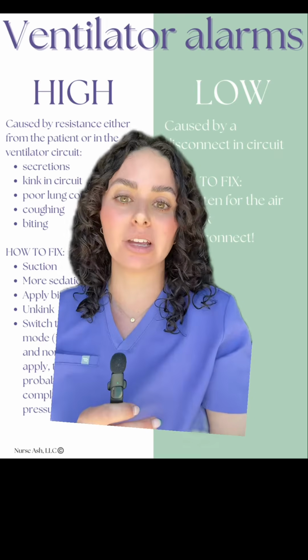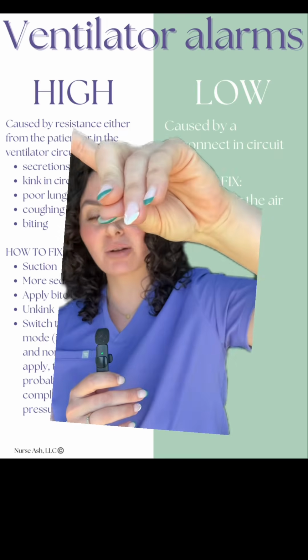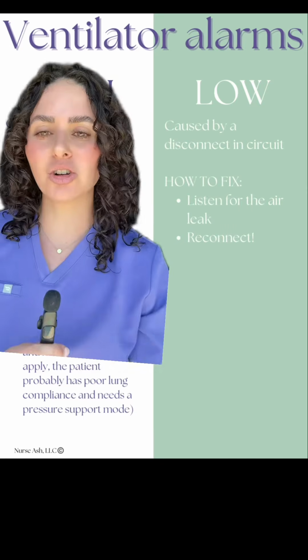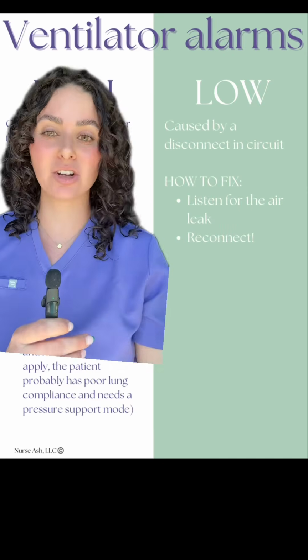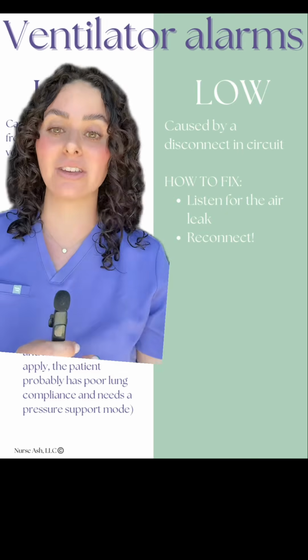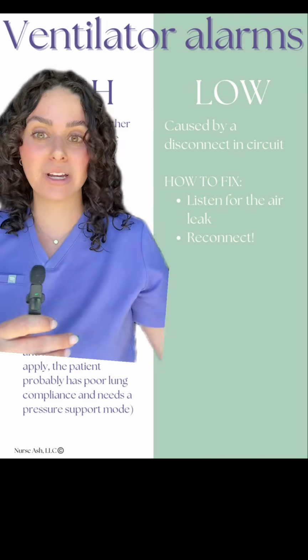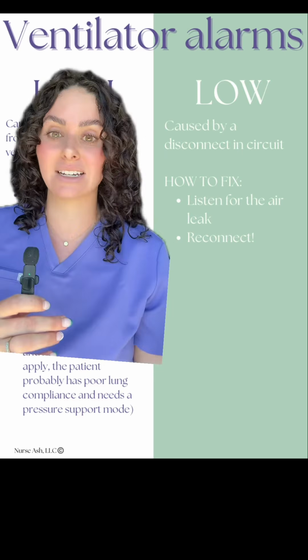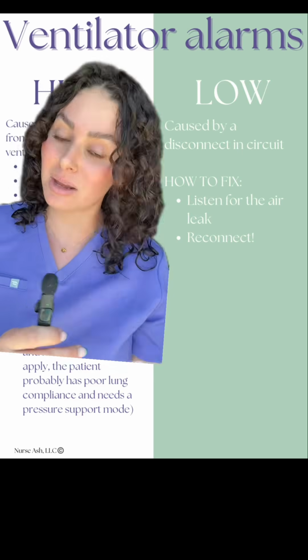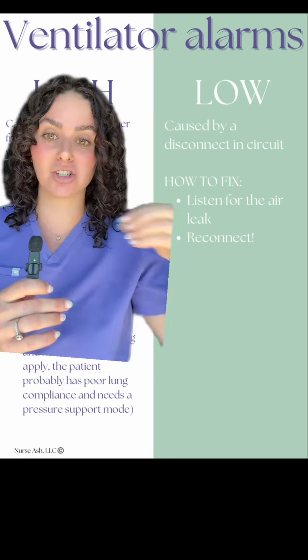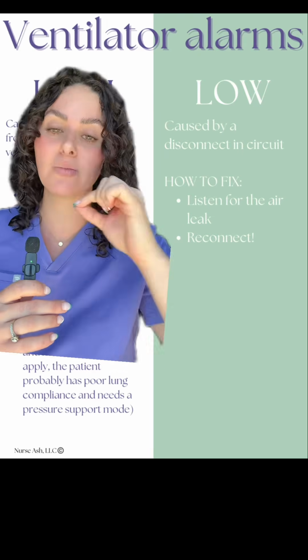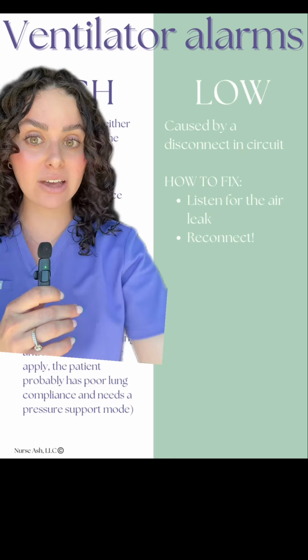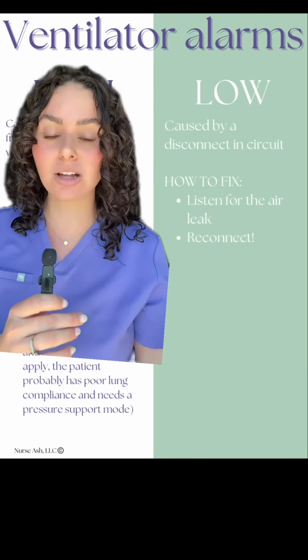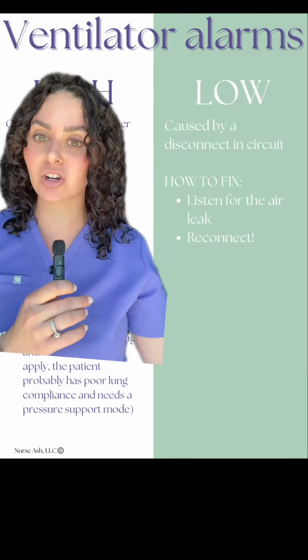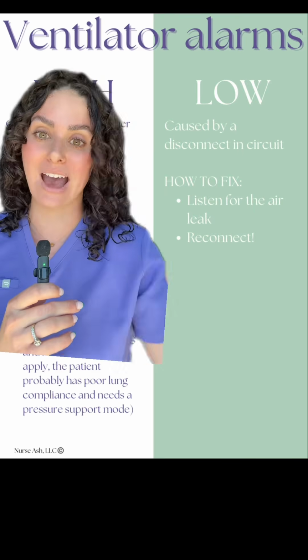There are two main types of ventilator alarms that you will most commonly come across. The first are high pressure alarms, and then there's low pressure alarms. Low pressure alarms are easier to troubleshoot because these are caused by a disconnect somewhere in the circuit. To fix this, you just need to reconnect wherever there is the disconnect. Now, the disconnect can happen in multiple locations. I've had the ventilator circuit disconnect right from the patient's ET tube. I've had it disconnect from the actual ventilator. There are quite a few connection spots, so definitely get familiar with your ventilator circuit as well as the ventilator that is at your hospital.